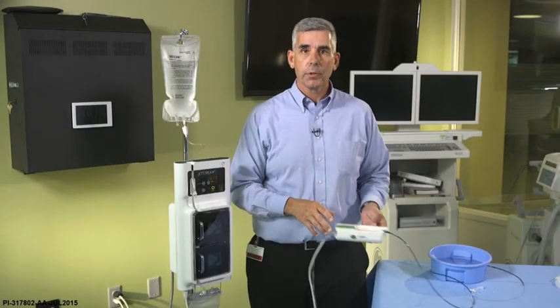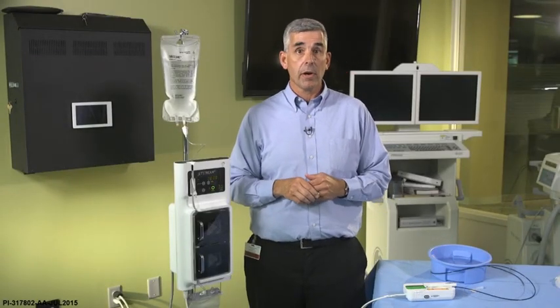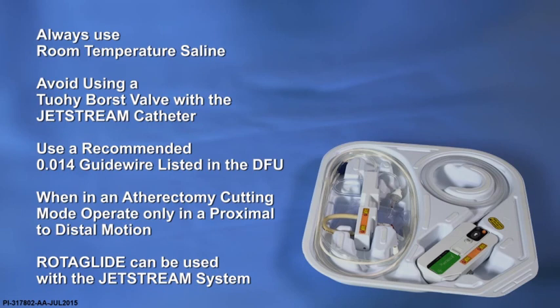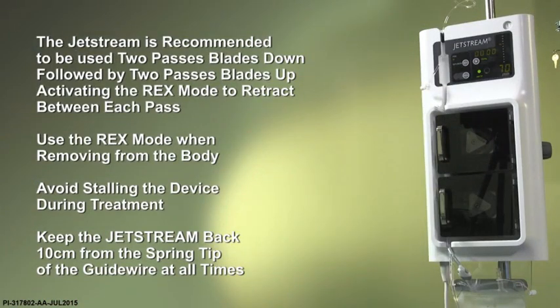Some of the recommendations when using the Jetstream atherectomy system and catheter are: always use room temperature saline. Avoid using a Tuohy-Borst valve with the catheter. Use the recommended 014 guide wires listed in our DFU. Only operate in an atherectomy mode in a proximal to distal motion. Rotaglide can be used with this system. The Jetstream device is designed to operate 2 passes blades down, followed by 2 passes blades up, with Rex activated when the catheter is being retracted in preparation for the next pass or for removal from the body.